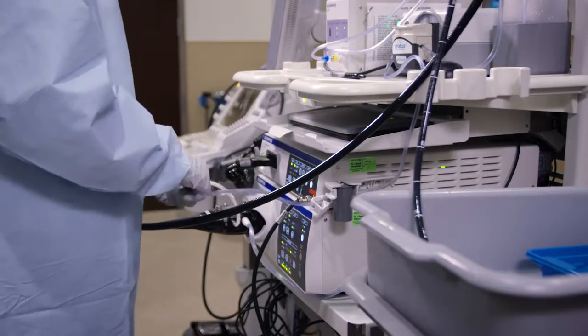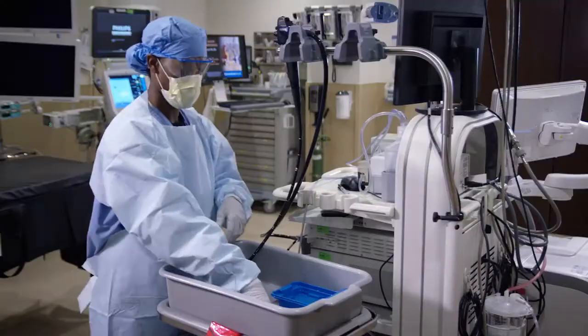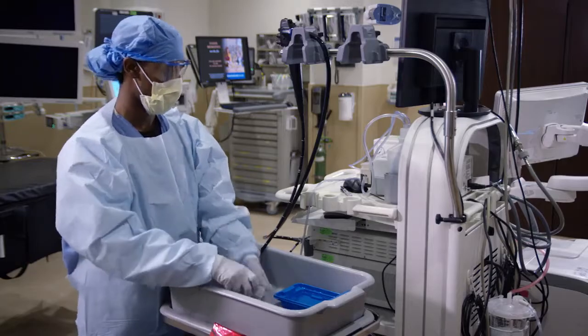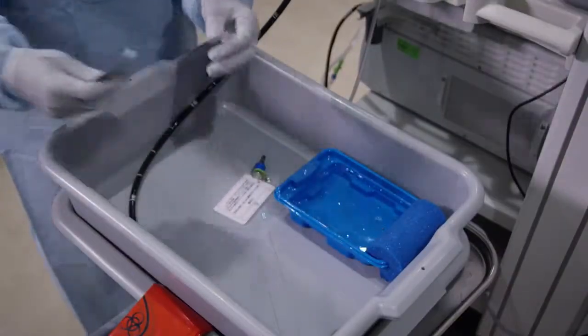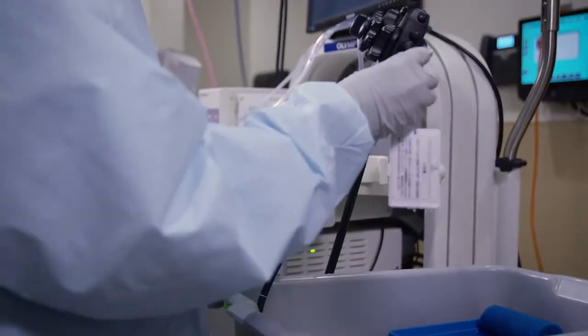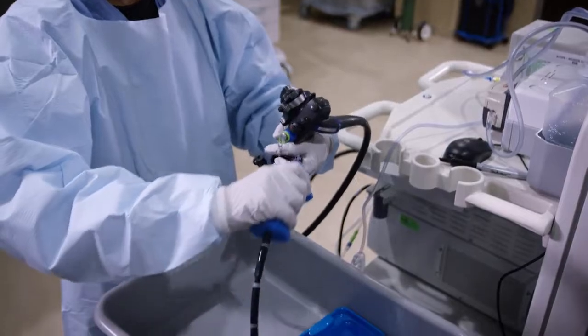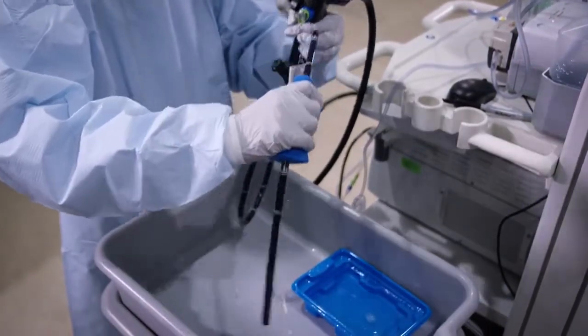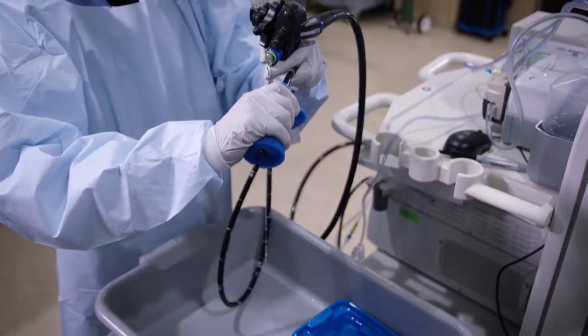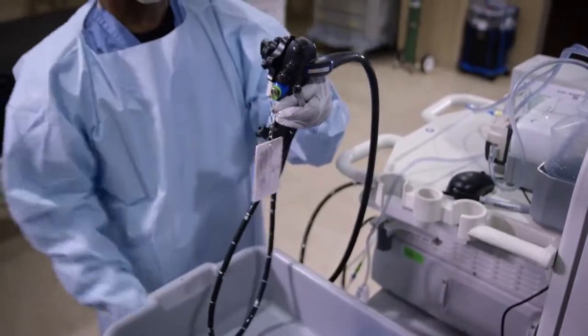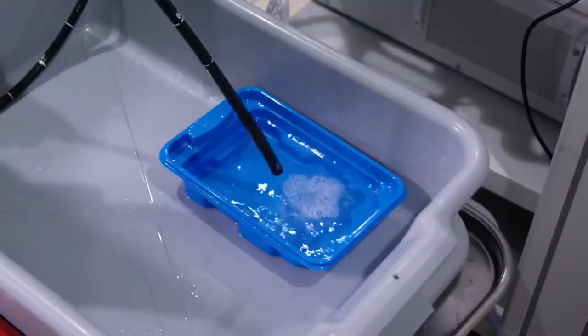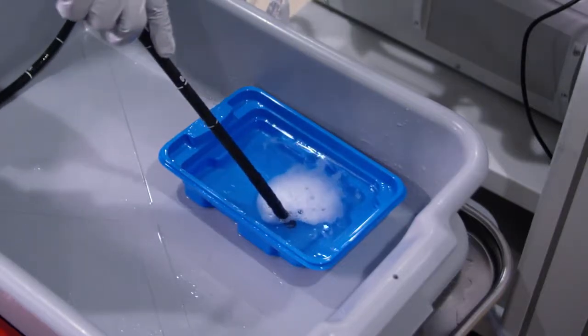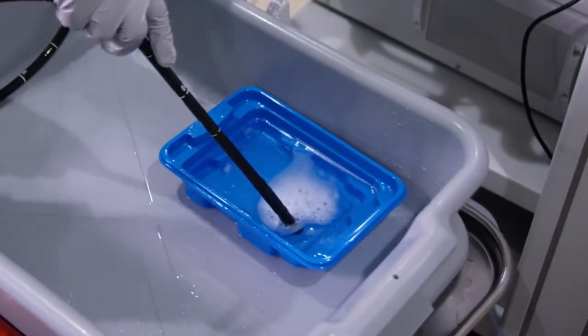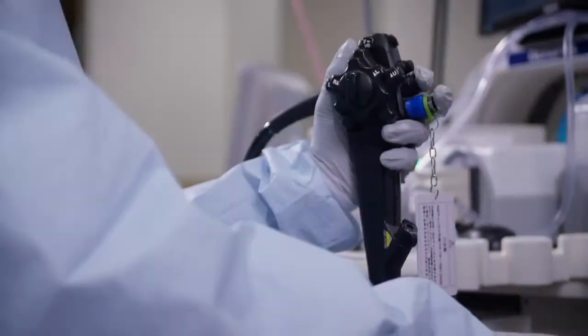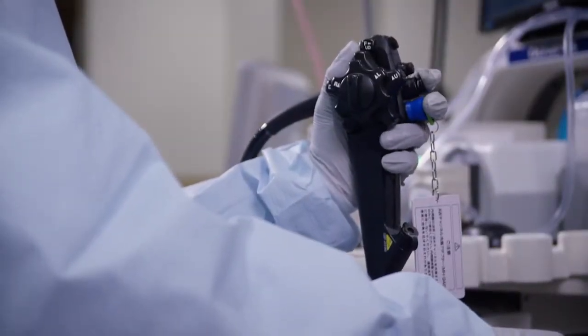Attach the water and channel connectors per endoscope IFUs. Prepare a container with a solution that is compatible with the device. If it's a videoscope, attach the protective fluid-resistant cap. To remove all gross soil, wipe the tube with a wet, disposable sponge soaked in solution. Dispose of the sponge afterwards. Place the distal end of the endoscope into the solution and suction the solution through the biopsy suction channel. Alternate solution and air several times.